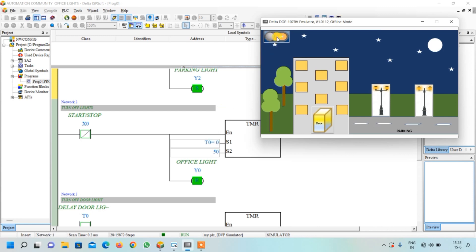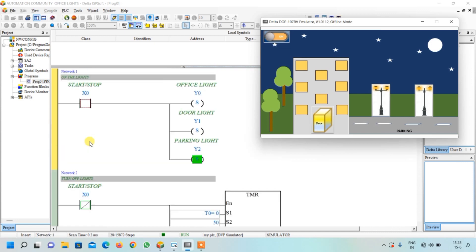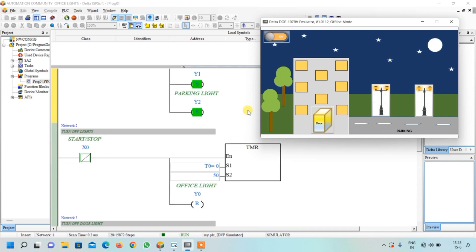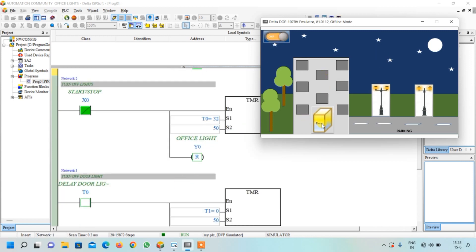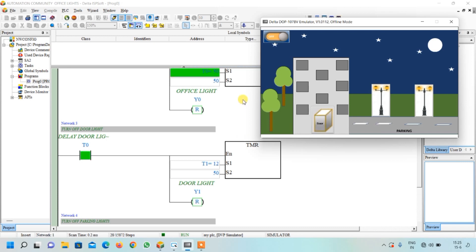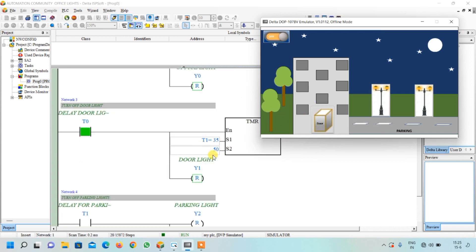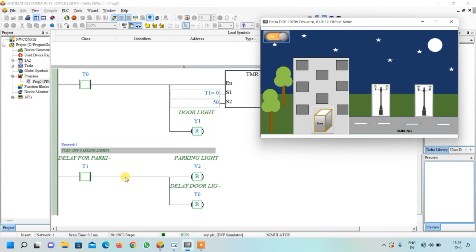Now as soon as I turn this switch OFF, the NO contact was ON, and when I turn it off, the NC contact becomes ON and the timer starts — the office light turns OFF instantaneously. But the door light stays ON, and after 5 seconds it completes and turns OFF. Right now it is counting 5 seconds, and after 5 seconds the street light is also OFF. All outputs are now in the OFF state.